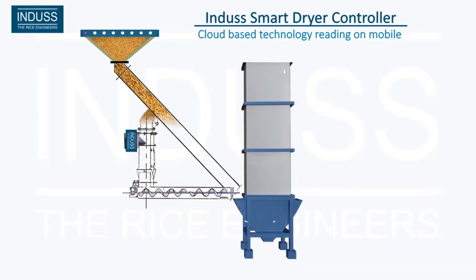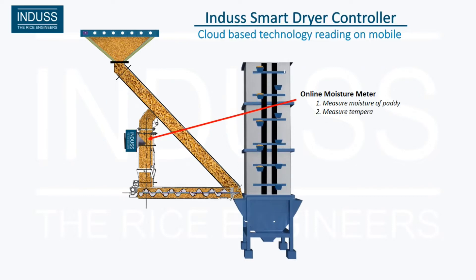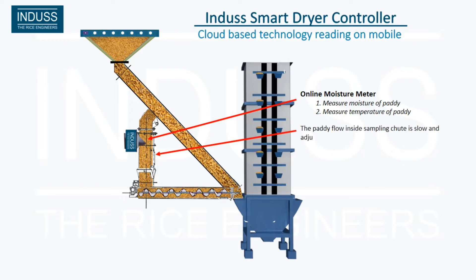PLC Controlled Online Moisture Meter. In a conventional dryer, the operator manually collects samples three times from the running dryer, then cools off the samples at ambient temperature. In the Induss Smart Dryer Controller, the steam can be cut off as per the set required moisture. Hence, the loss due to over-drying can also be prevented.